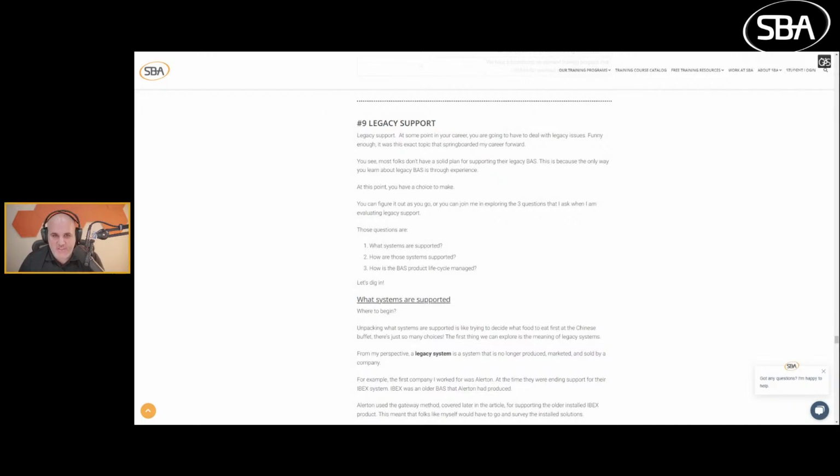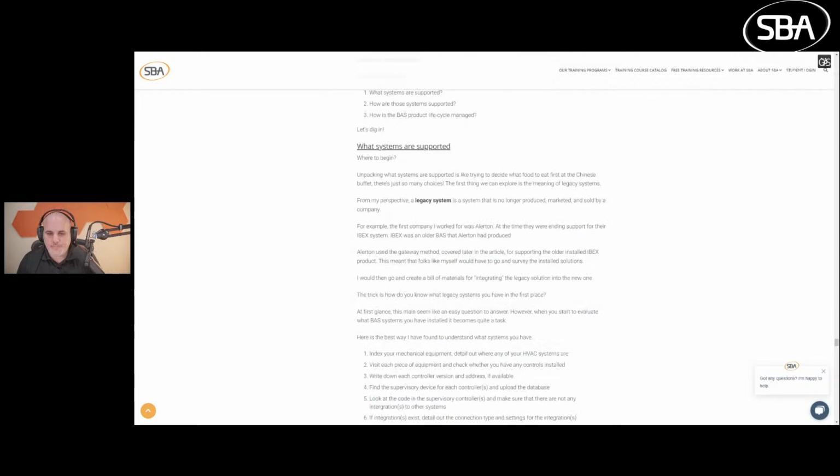Nowadays, we see control systems that really are starting to have massive changes to their architecture or software. You've got IP controls, you've got BACnet SC coming down the pipe, which, as far as I can tell, will require firmware updates and potentially controller replacements for legacy products. So having legacy support is really important. You want to understand this, especially if it is a large purchase. I don't recommend this for a $20,000 job. But if you are investing in a $5 million control job, you darn well better ask, what is that manufacturer's plan for supporting legacy products through the life cycle of the building?